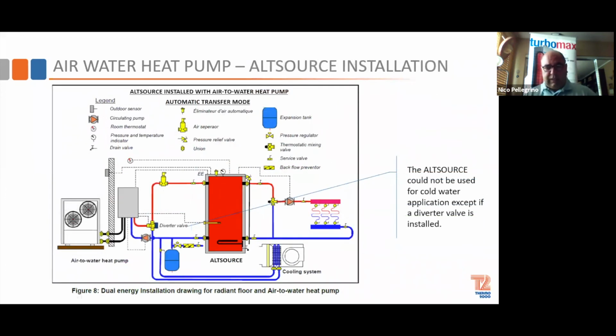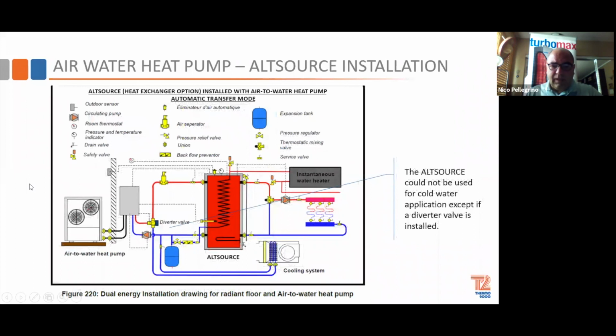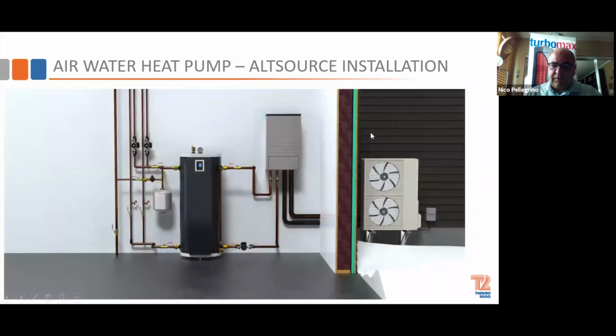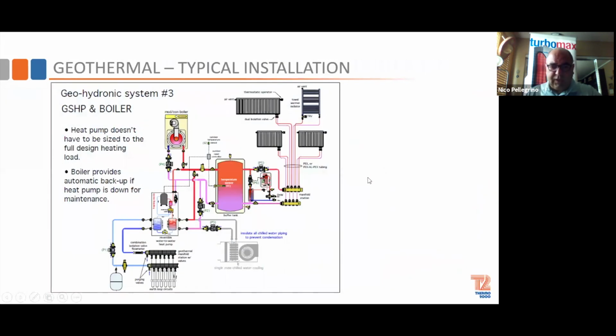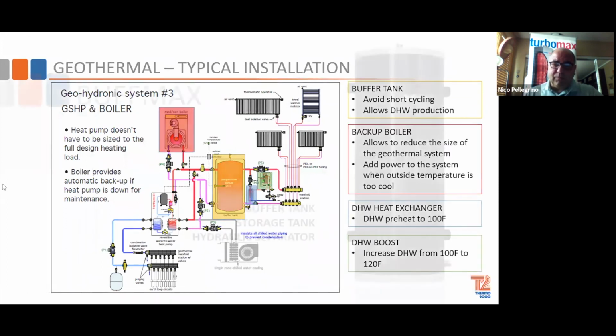Again, if you're going with the ALTSOURCE, the only difference is that if you're doing air conditioning, you need a diverter valve applied to the system because this tank is not designed for chilled water. So if you're doing preheat for domestic water, then you need to finish it off with a domestic tank or instantaneous. Geothermal, same thing, and again, it's basically one tank does it all.